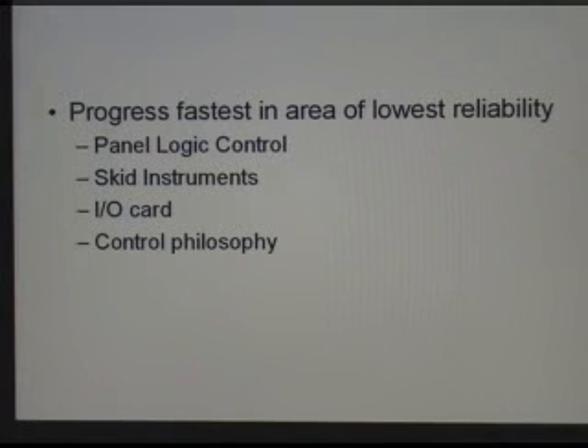Now, progress on the control systems has been fastest in the area of the lowest reliability. So, the panel logic control relays are about the least reliable thing that you can get for controls. Mechanical devices, they physically have to move, make contact. Corrosion will prohibit them from working. High cycle fatigue will cause failures inside, which will prohibit them from working. Vibration may actually move them within their slots so that they're no longer in electrical contact with wires, which will prevent them from working. So there's all kinds of ways that relay logic could fail.